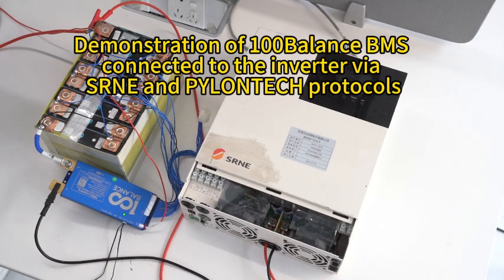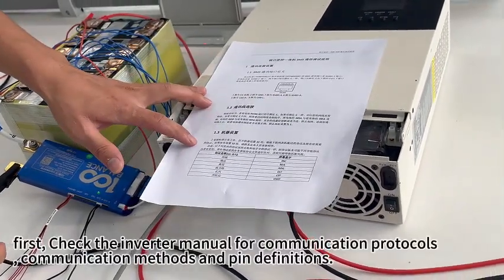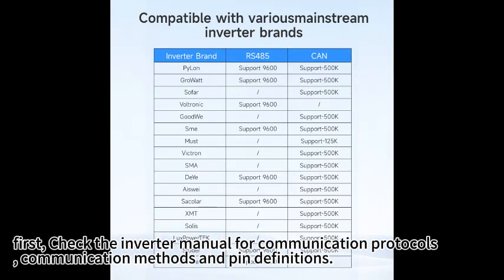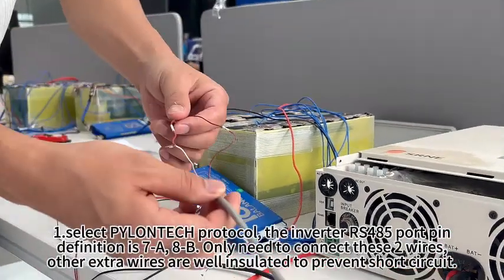Demonstration of 100 balance BMS connected to the inverter via SRNE and Pylontech protocols. First, check the inverter manual for communication protocols, communication methods, and pin definitions. First, select Pylontech protocol.